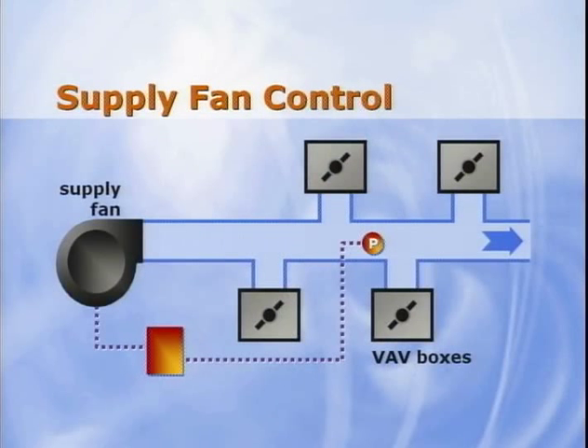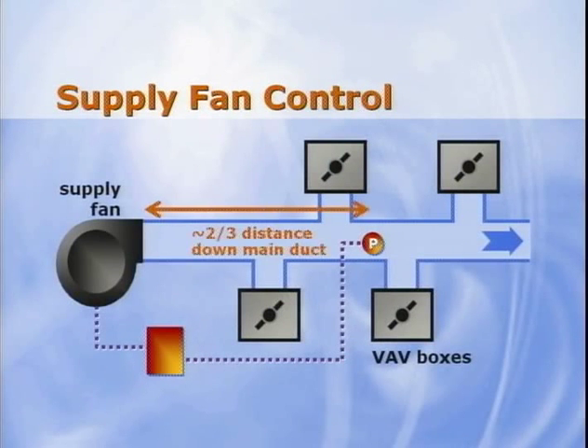In a VAV system, as the cooling loads in the zones change, the VAV boxes modulate to vary the airflow supplied to those zones. This causes the pressure inside the supply ductwork to change. The rooftop unit modulates the airflow of the supply fan to maintain the set point of the supply duct static pressure. In many systems, the pressure sensor is located about 2/3 of the distance down the main supply duct.